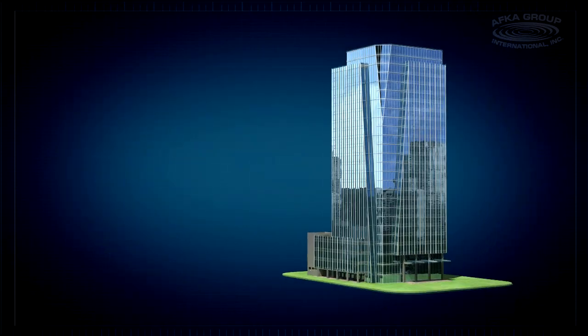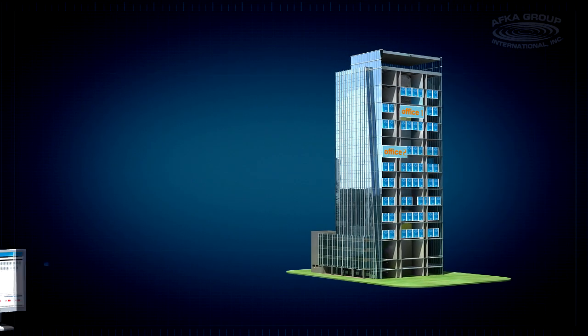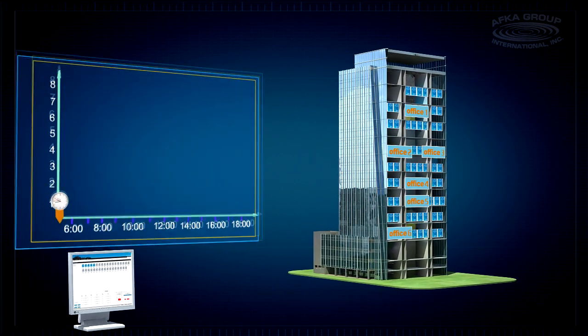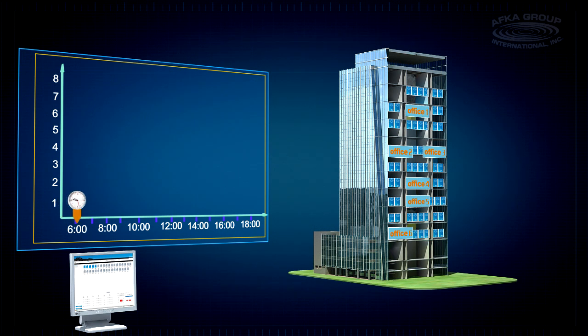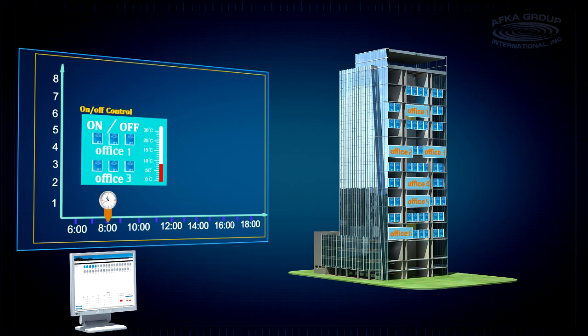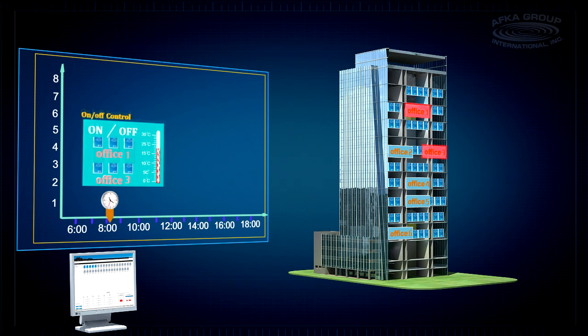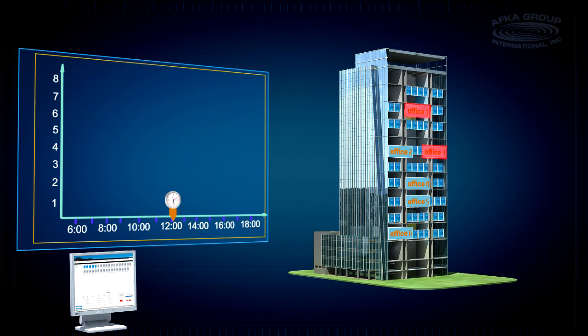Afka Group provides accurate schedule control, which automatically performs facility start-stop control, switching the operating mode, setting temperatures, and enabling or disabling the remote control according to the preset time schedule. Maximum 4 sections and 10 actions per section in each day for each single unit or group.